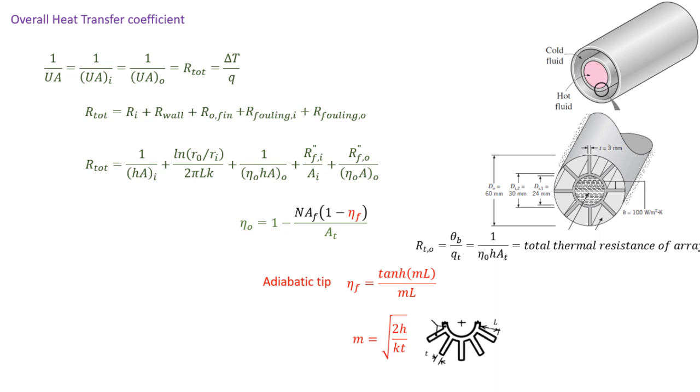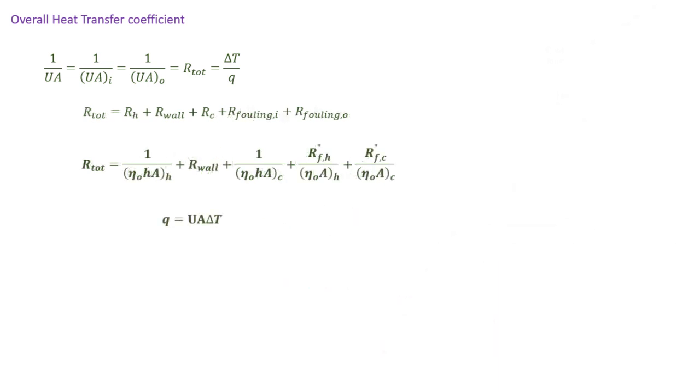In more general terms, this is the equation for the overall heat transfer coefficient. It takes into consideration that you may have fins on the hot side or the cold side. It also takes into consideration that you may have fouling, and if you don't have fins on the hot side or the cold side, just replace those efficiency terms with one.